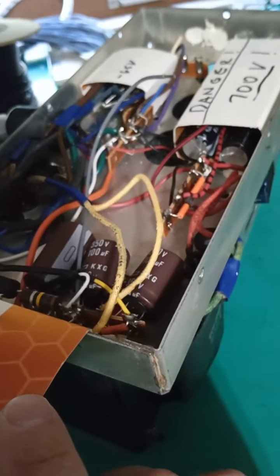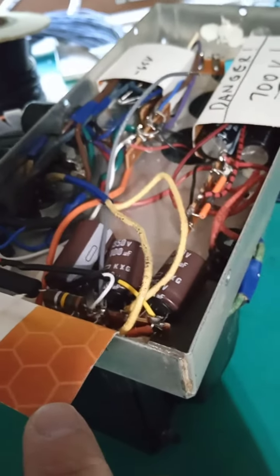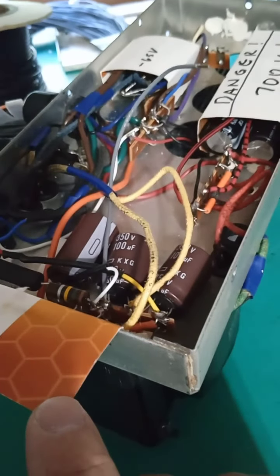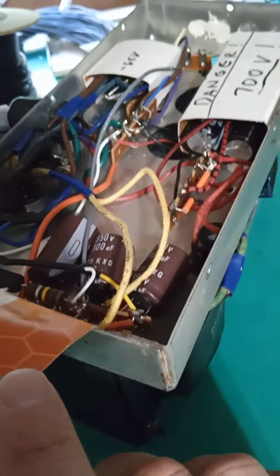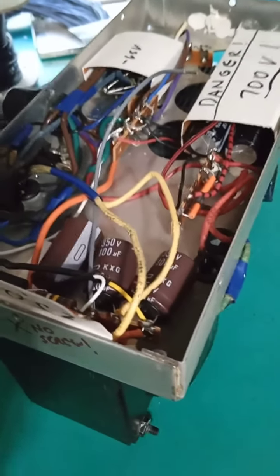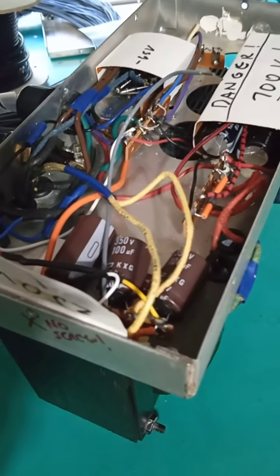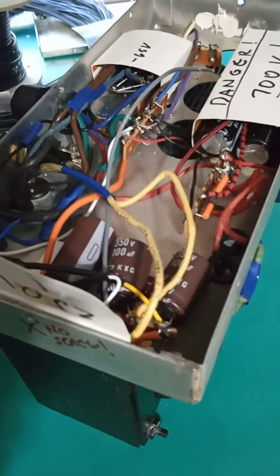That's good. There's a thing with transformers called phasing. There are no phasing dots or marks usually on a simple power transformer, but there's always leakage, and power transformers are not isolation transformers and not specifically designed to minimize leakage.